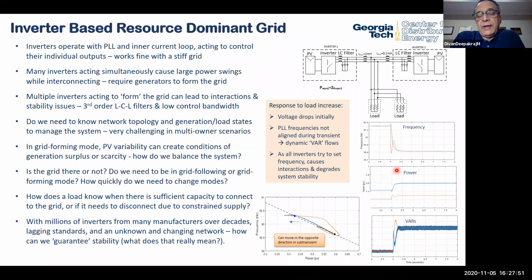One thing I do want to talk about is that as we start seeing a system that is more heavily inverter-based on the grid, the question becomes how do you control them? I'm sure your teams are working on this problem too, but I think there are a few gap areas we need to cooperate on and address. A typical inverter operates with a PLL and an inner current loop. When you have large power swings, you can have problems with inverters. Typically we've designed these systems so there's a generator that really forms the grid, and all the inverters work together with it. Now, when you try to form the grid through inverters using PLLs, it doesn't work very well because they all fight with each other. I know Phil's been working quite a bit on some of the issues associated with this, including some of the resonators and everything else.